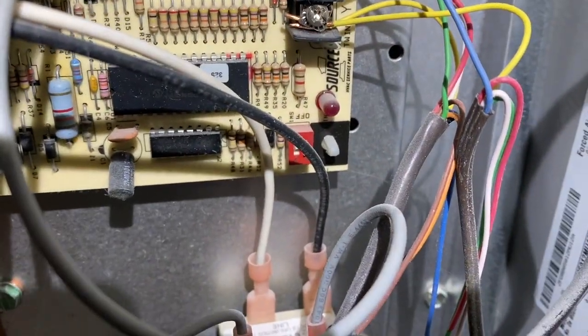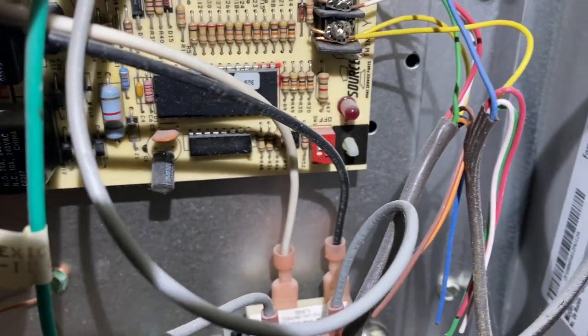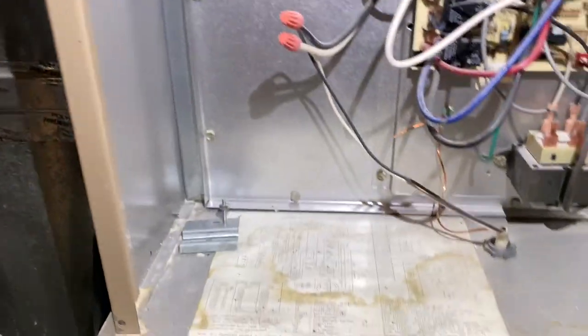Let's take a look at our error code here — one, two, three, four. We've got four flashes. Let's see what that is. Gotta find the code book first. Four flash, four flash — limit switch open. So that's our limit switch.